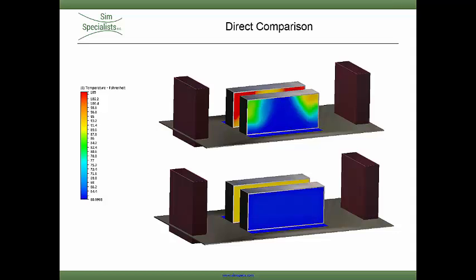The hot aisle containment increases the room's efficiency by 25%, in this case reducing the operating cost by over $40,000 per year.